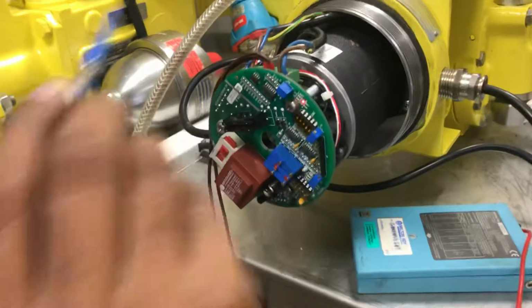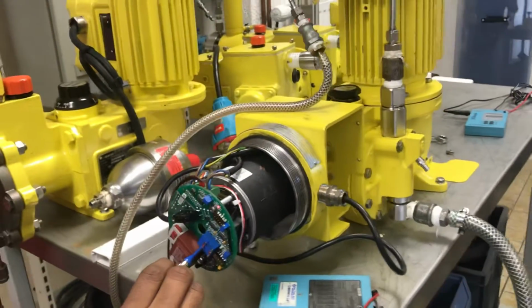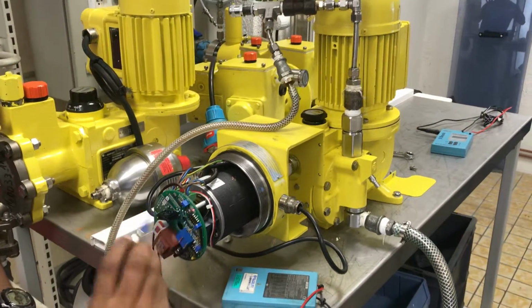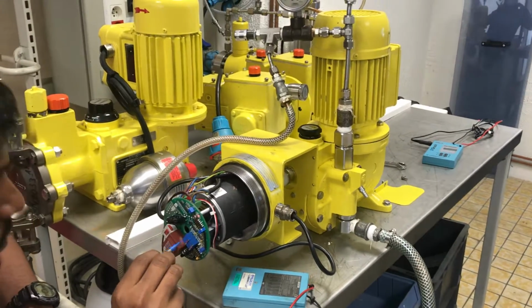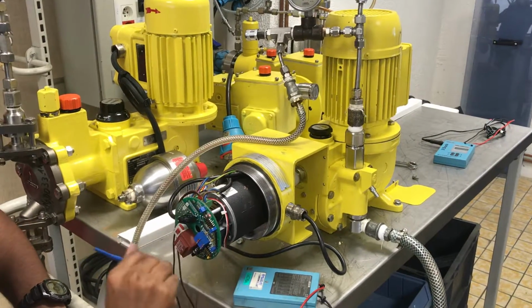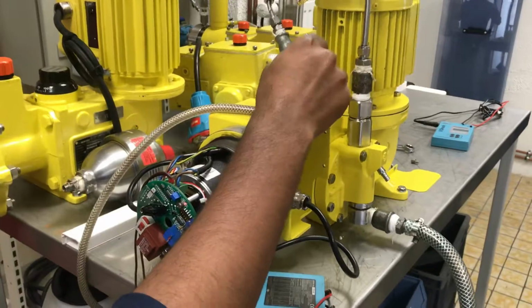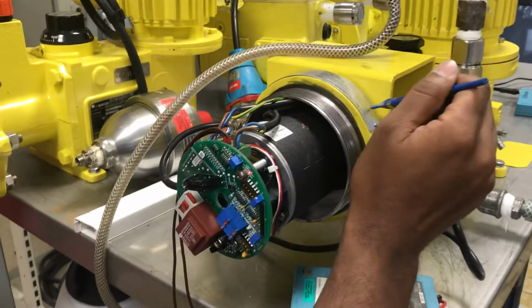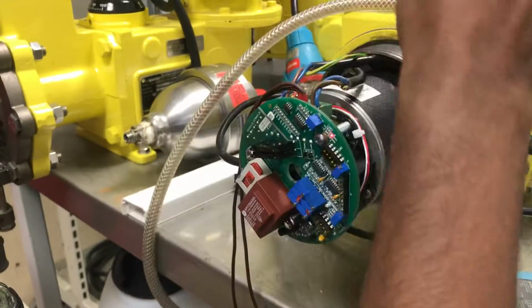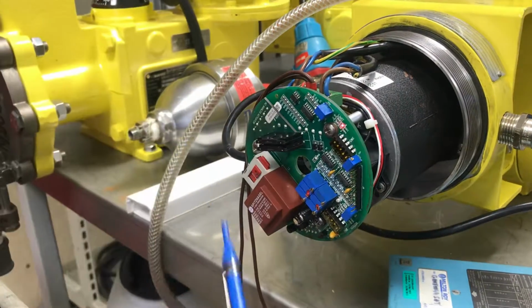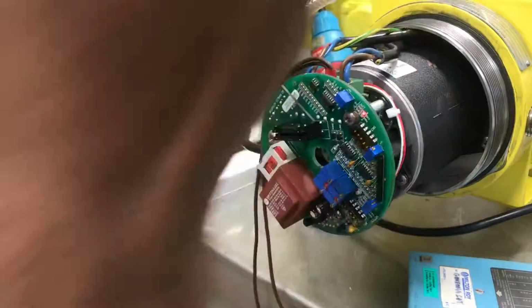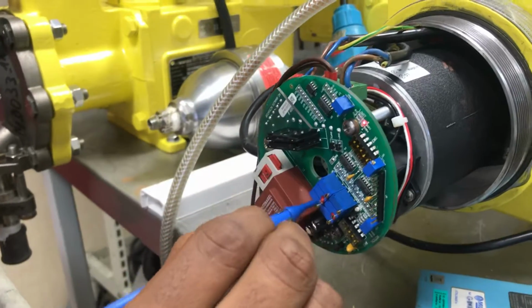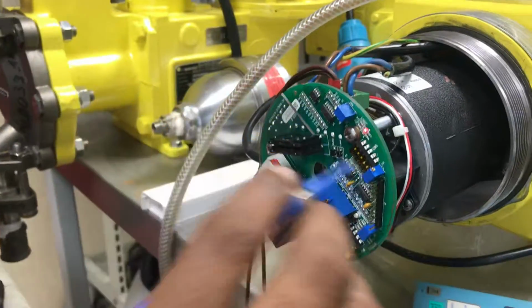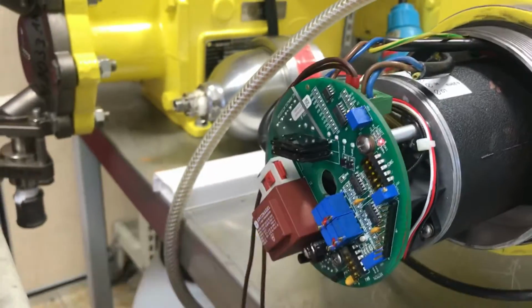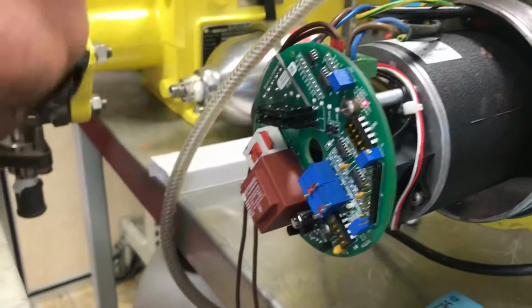Now in this pump we have 8 turns, so what we need to do is adjust this screw until this light turns off. Then you make the adjustment on this screw, either clockwise or anti-clockwise, and physically check the number of turns. Example, if it is 8 turns and you turn clockwise, you check whether 2 turns are rotating or not. So now 2 turns are added. So again you lock this and make the yellow light. So now we set it 0 to 100%.